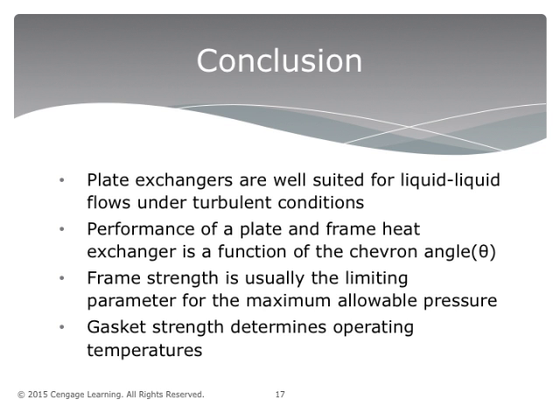In conclusion, plate exchangers are well suited for liquid-liquid flows under turbulent conditions. These exchangers can also be used as condensing units operating at moderate flow rates and pressures up to 60 psi. The performance of a plate and frame heat exchanger is a function of the chevron angle, which is the angle made between adjacent ribs and the vertical for a herringbone pattern plate. The maximum allowable pressure of the fluids is determined by frame strength, plate deformation limits, or gasket retainment ability. Frame strength is usually the limiting parameter for the maximum allowable pressure. Operating temperatures are usually limited by gasket strength or tendency to decompose.